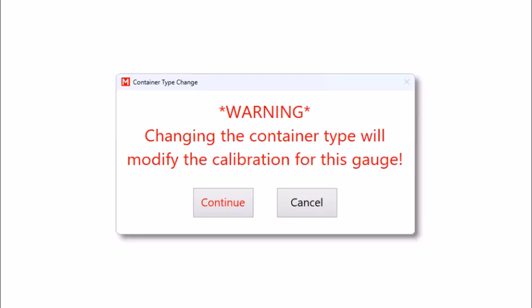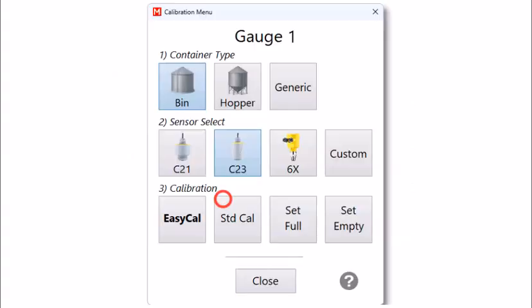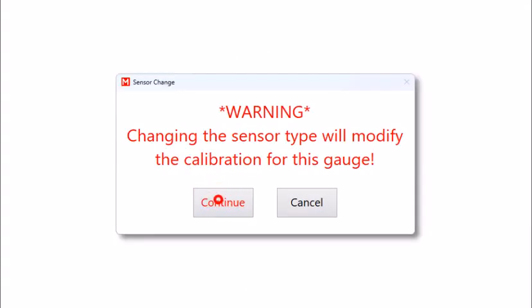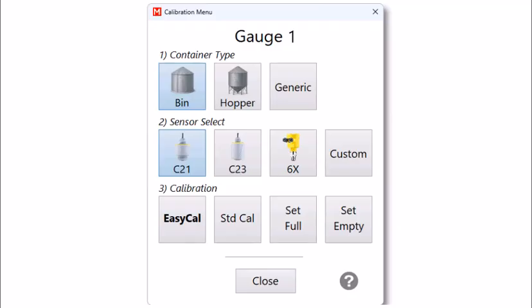At each step through this process, you will need to acknowledge a pop-up that indicates you will be modifying the calibration for this bin. If you select the standard bin type, you'll have access to all of the calibration options. Select your sensor type. We'll pick the standard C21 for this demo. And then choose the calibration option that best fits your needs.